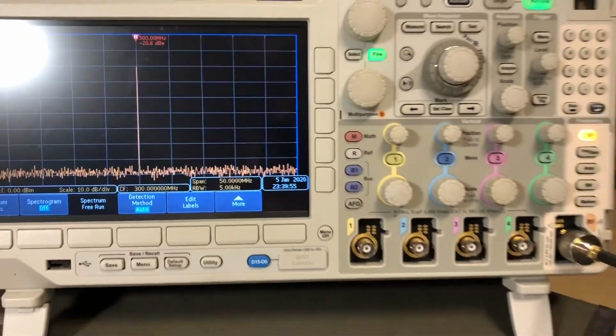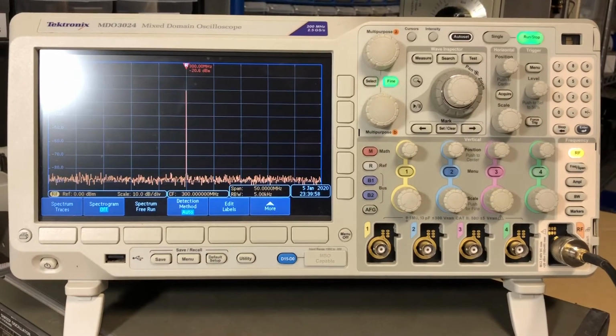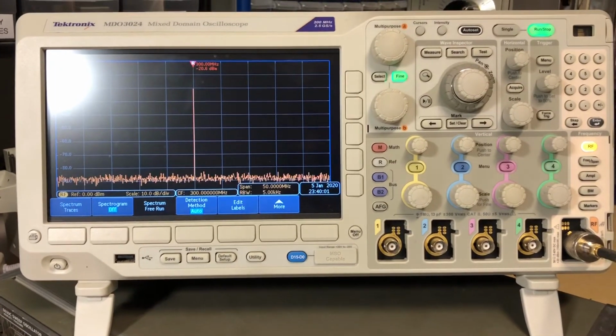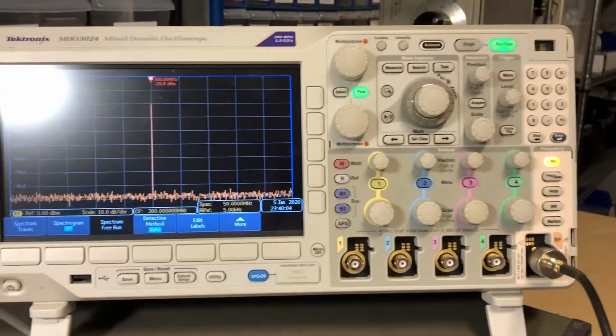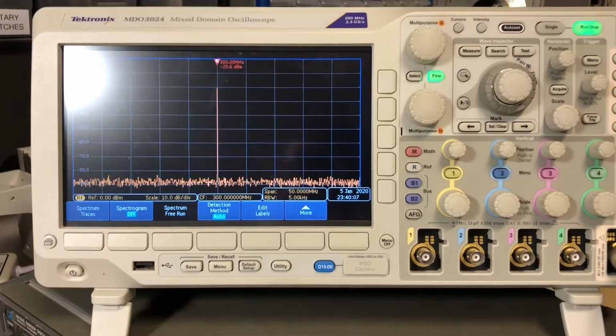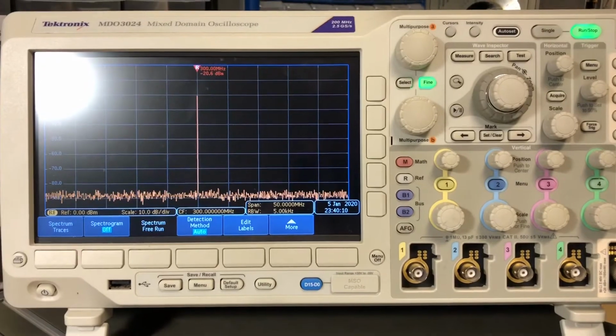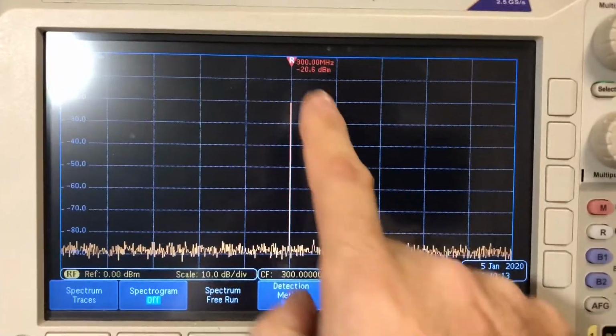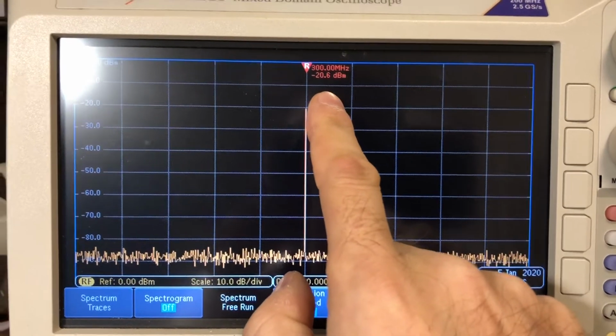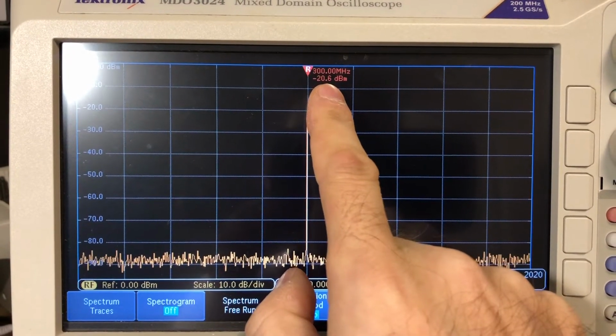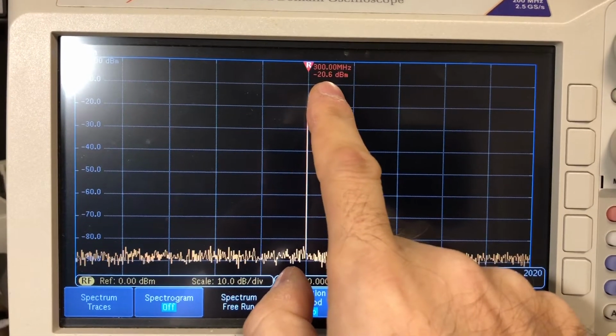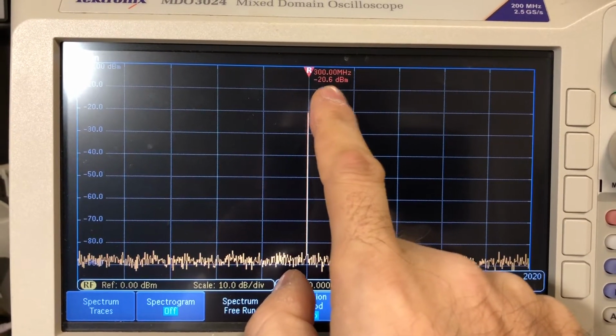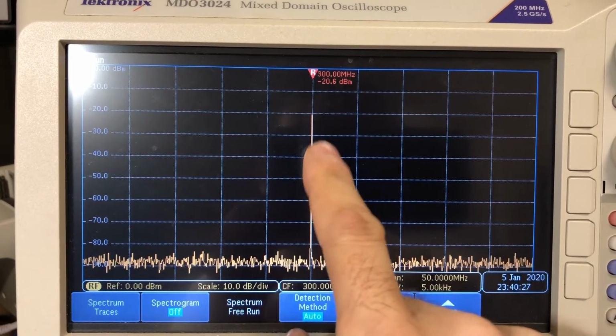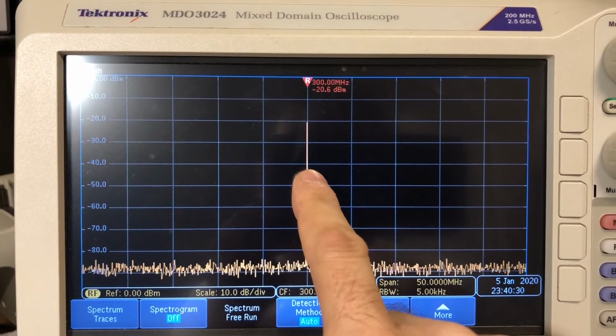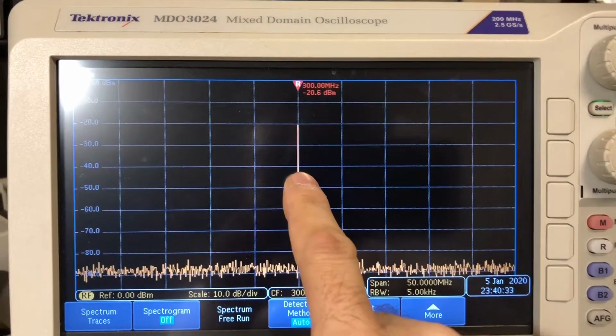So we've got our reference spectrum analyzer set up, and this is the next best analyzer I have for the 6.5 gigahertz band. This one will go to 3 gigahertz, so it's going to get us part of the way there. If we have to do extensive troubleshooting, it's not going to get us all the way there. But here's our cal out signal. We're looking at right at 300 megahertz and minus 20.6 dB, minus 20.6, 20.7 dB. So that is well within our specified level for our cal out signal.